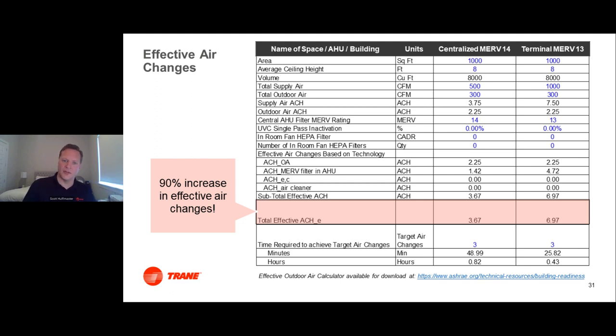But what if I've got a terminal unit that's a constant volume of air, like a series fan powered box, and I'm able to retrofit that or maybe purchase it from the factory with a MERV 13? Well, believe it or not, when I'm able to do MERV 13 in the space, I'm getting almost a 90% increase in effective air changes. Effective air change is the amount of clean air in the space because I'm putting a lot more air through a MERV 13. And even though the MERV 13 may provide slightly less removal than the MERV 14, filtration is very dependent upon the amount of air you put through the filter. So this is just something to consider.